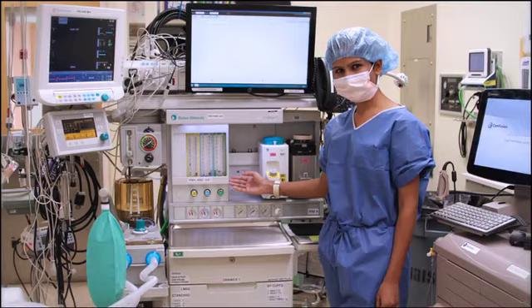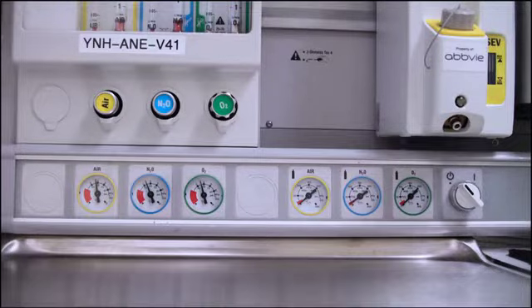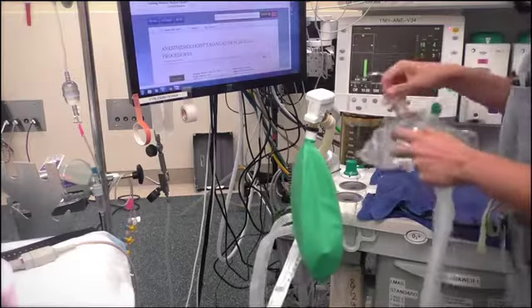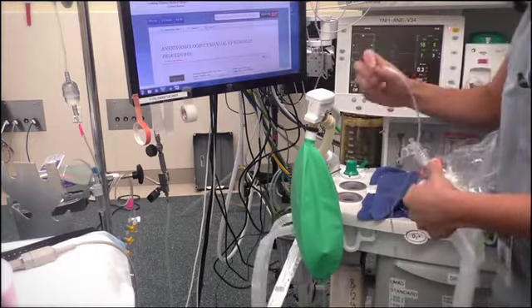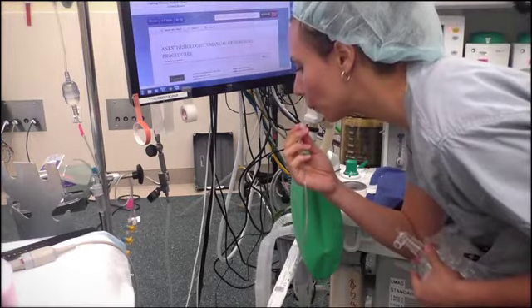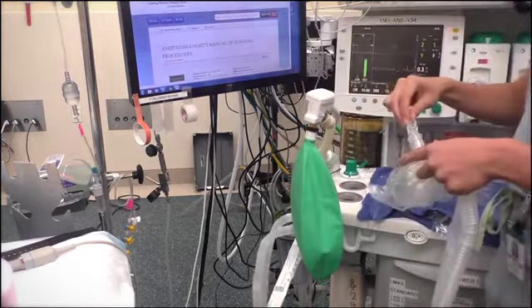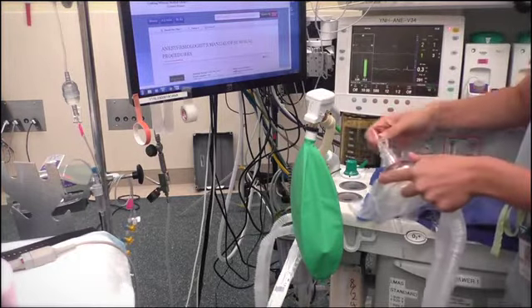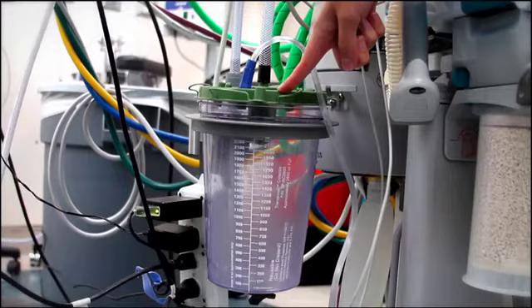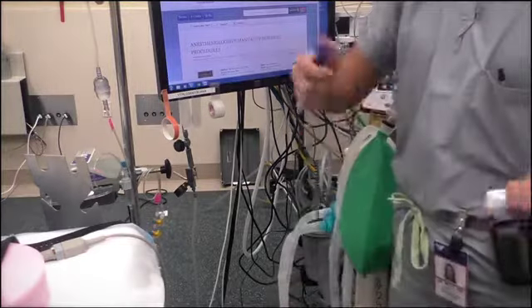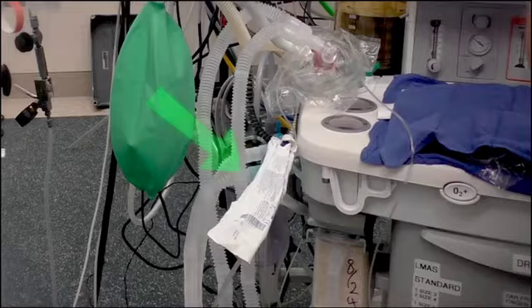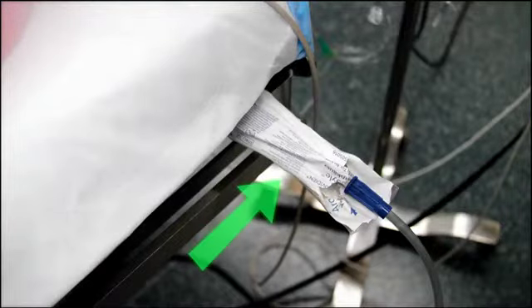In older models, shown here, check that there's enough oxygen pressure from the main source and the O2 tank on the gauges. This may not tell if the source is disconnected, however. The full machine check will reveal this. Next, disconnect and blow into the gas sampling line and check for end-tidal CO2. Then, reattach the sampling line. Check that your suction setup is complete with canister, tubing, and Yankauer tip, and that it's working. Make certain the tip is readily available near the head of the bed.